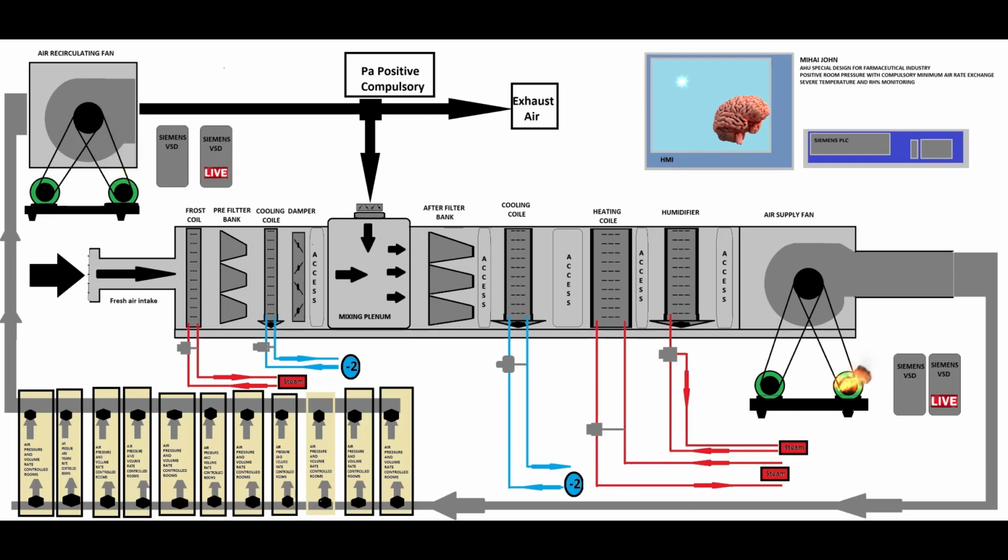You have the human machine interface and the PLC, which constantly monitor the function of the system. If this happens, the PLC will give an instruction to this inverter to stop motor number 1 and will transfer the function to inverter number 2 to start motor number 2 to take over. But it's supposed to be only an electrical failure, because if you have a mechanical failure, unless you have a broken belt, you might disturb the other motor.